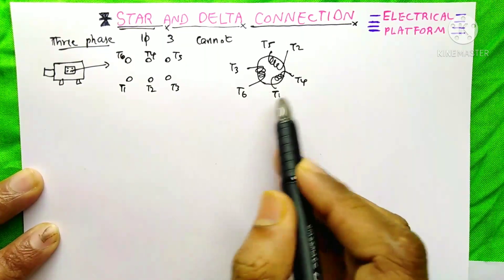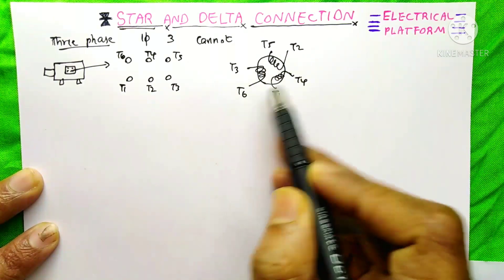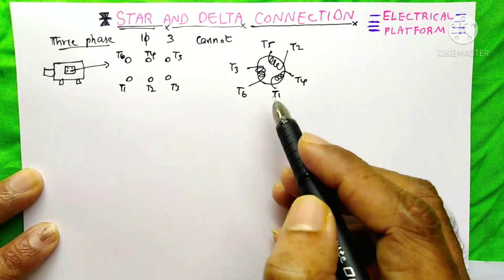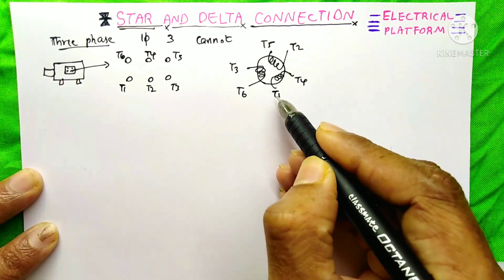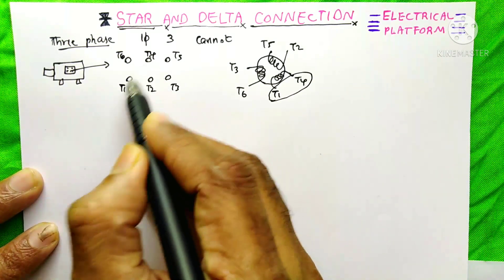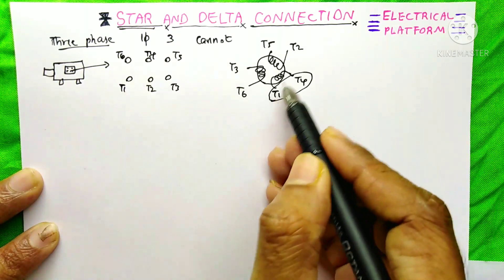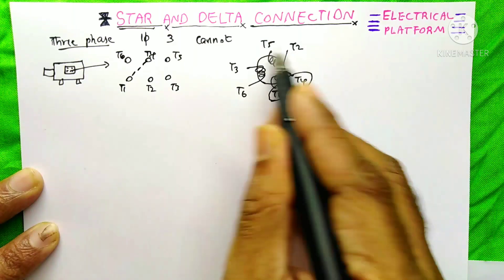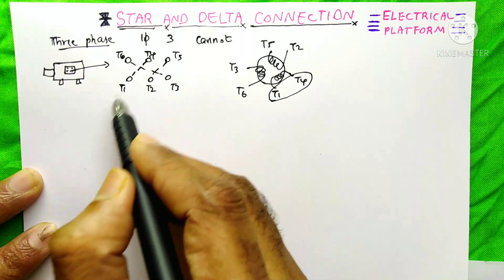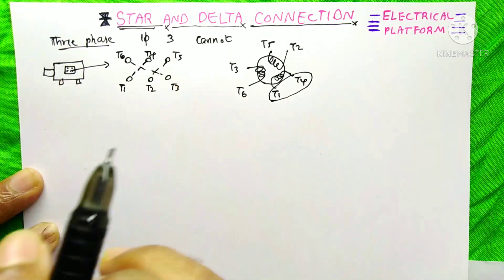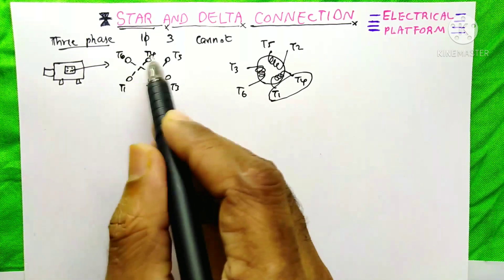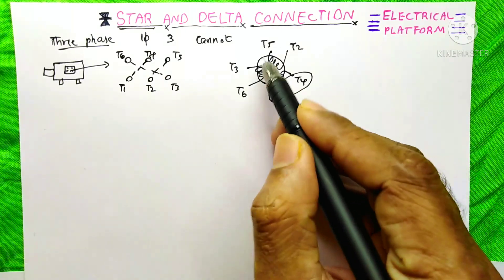This is the stator inside the three-phase motor. There are three windings, and each winding has two terminals: T1 and T4, T2 and T5, T3 and T6. So T1 and T4 are interconnected, T2 and T5 are interconnected, and T3 and T6 are interconnected. I have drawn a dotted line for your understanding. When we look at the terminal box, we cannot see this connection — it is only shown on the stator.